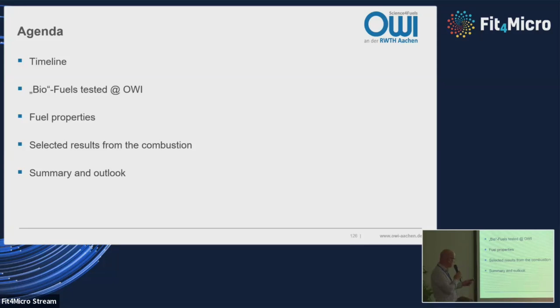The first projects started with optimization of burners for domestic applications, for combustion of domestic heating oil. The challenge was reducing emissions of CO, residual hydrocarbons, and NOx. In 2001, sulfur content was reduced for domestic heating oil, limited to 1000 ppm for standard oil, and low sulfur domestic heating oil was introduced with a maximum of 50 ppm. It was found that low sulfur heating oil leads to fewer residues in the combustion chamber.